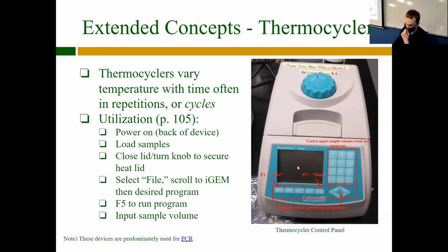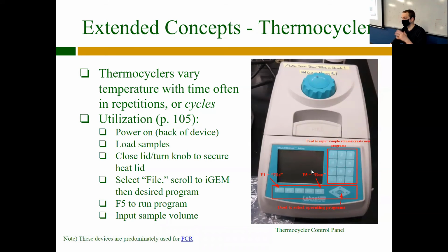Next, because it's turned on, there's going to be a little GUI here. And you're going to select F1 for file. It's going to take you to all the programs we've made in the past. Next, scroll to iGEM. You're going to use these little up and down arrows to scroll to iGEM and select the desired program by clicking enter. After that, it's going to bring you to the stats of the program, where it's going to tell you what the program's doing and how many repetitions it's going to be doing of it. And you click F5 to run, then it's going to ask you to input your sample volumes, and you just put in the volume that you have suspended within your tubes. Depending on the procedure or the cycle that you're running, it might take anywhere between 40 minutes and an hour and a half to finish. It's dependent on what you're doing with the Thermo Cycler.